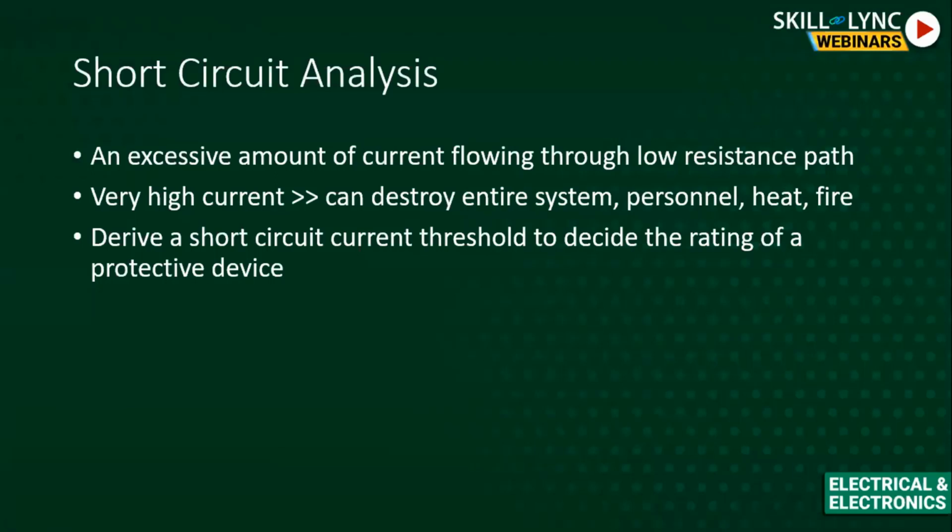So how does the short circuit analysis help us in designing the power system and the protection devices connected to it? It is very much necessary that, if there is a generating station, a transmission line and a distribution, we must analyze what the fault level is, because if I have to design a protection device, I must know the voltage and current level for which I am designing the product. So this analysis is carried out. There are various software tools used for such analysis to get an idea: if I'm suggesting a protection device for this feeder, these are the voltage and current levels.